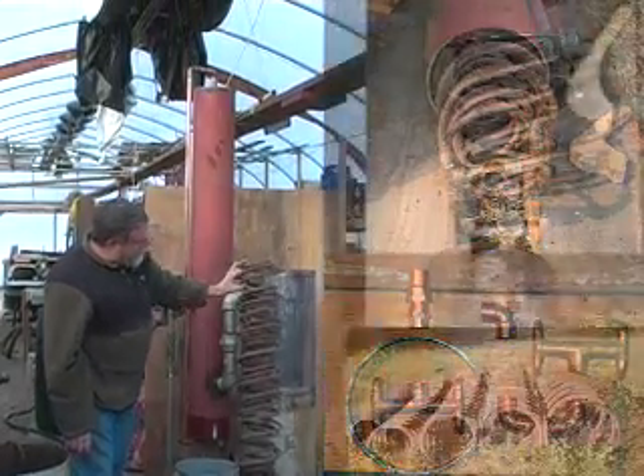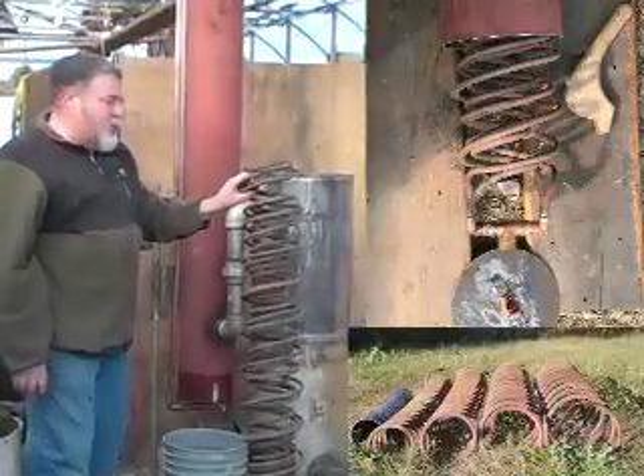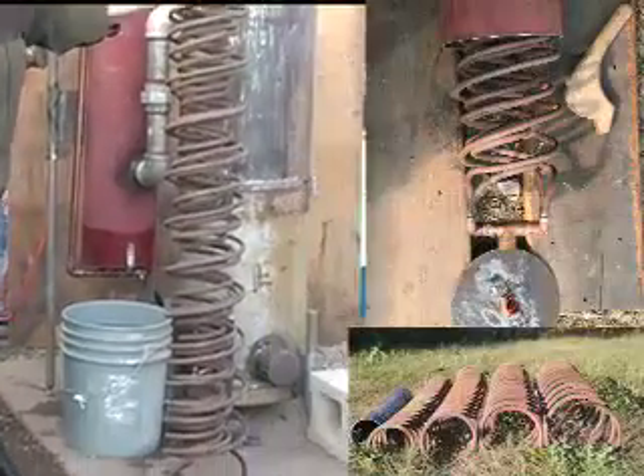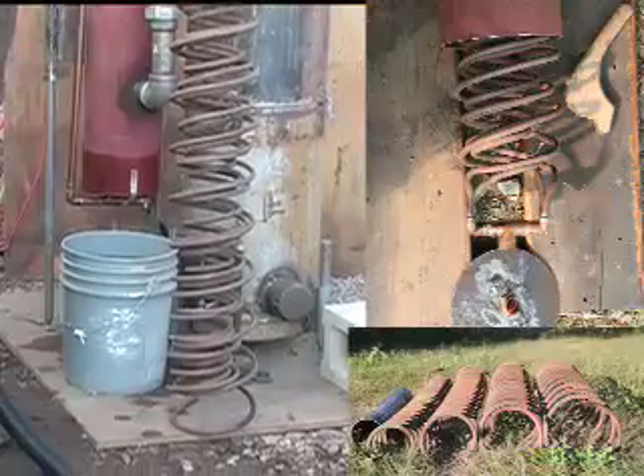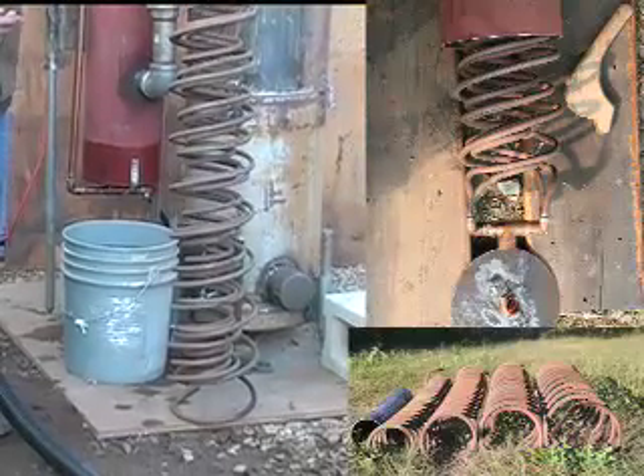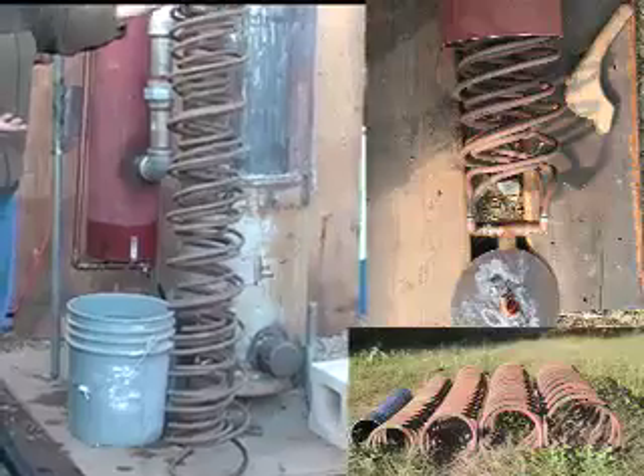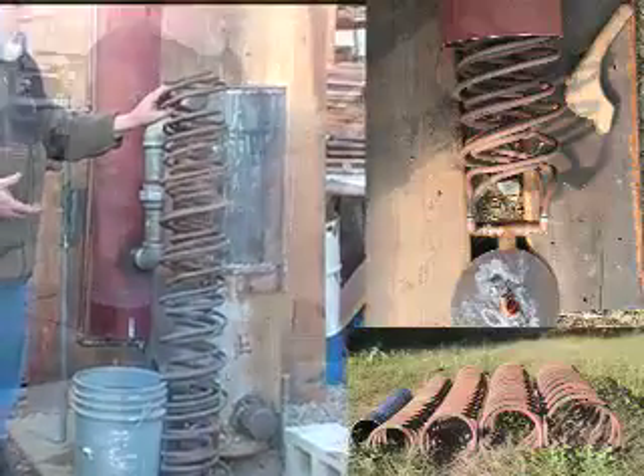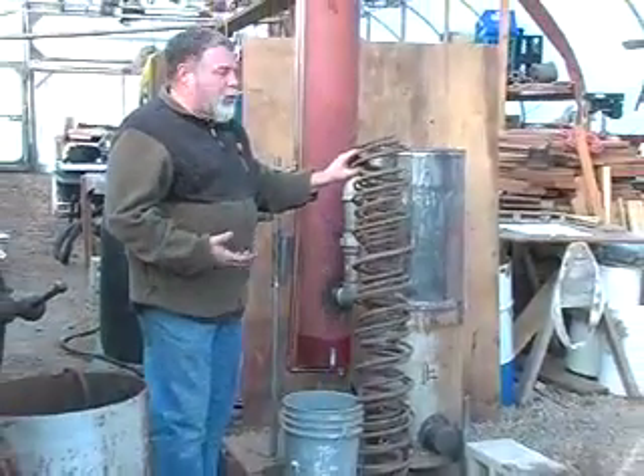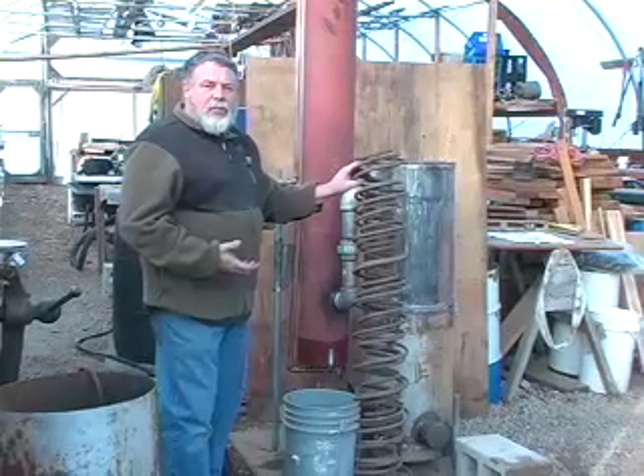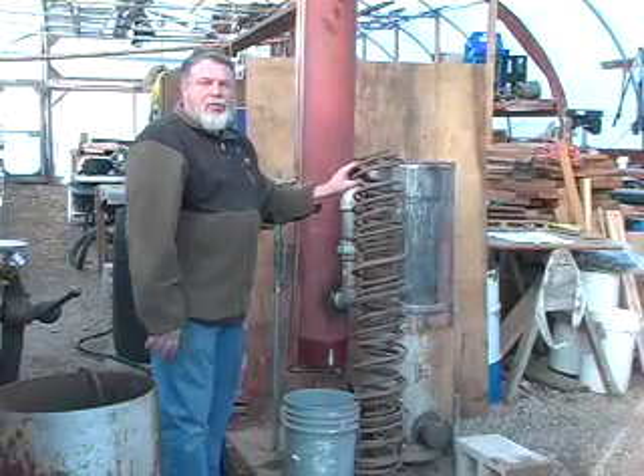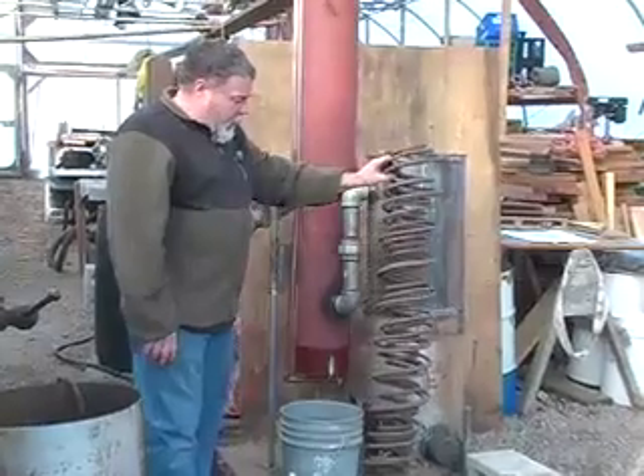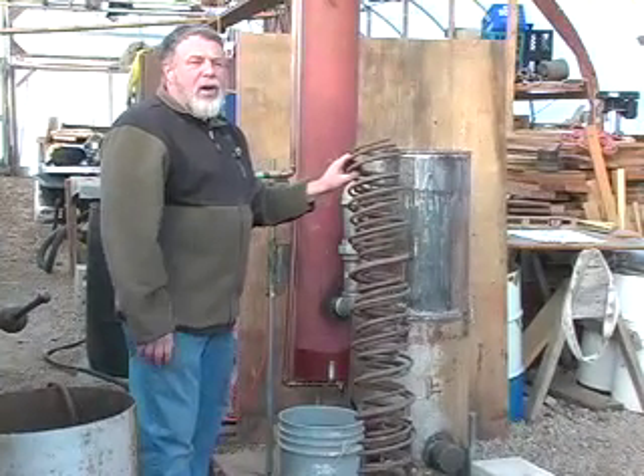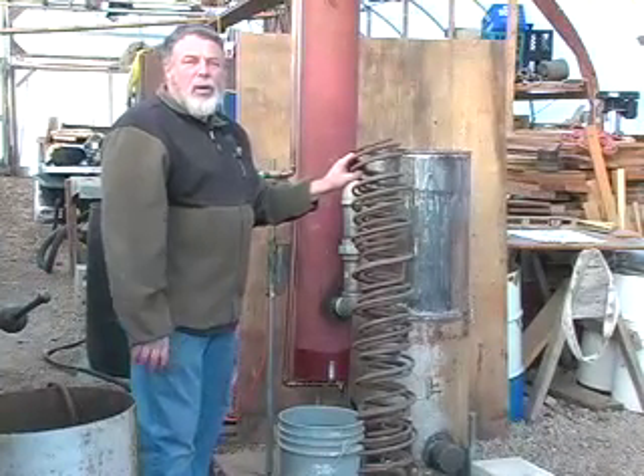Each one of these coils, which there are four of them, has about 24 feet of copper in it. So by coiling them together, as the gas comes up through it, it has a lot of surface area to be cooled or to come in contact with the gas to cool off. Through these we pump water, and we can recover some of the heat that is lost. It would normally just be lost, in radiation. We can now recover it and use it for anything from hydronic heating for hot water or whatever we want to use hot water for.